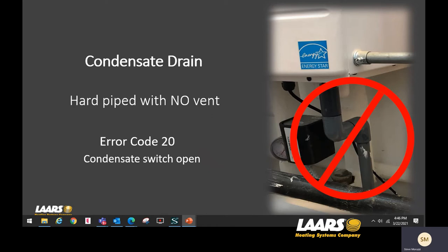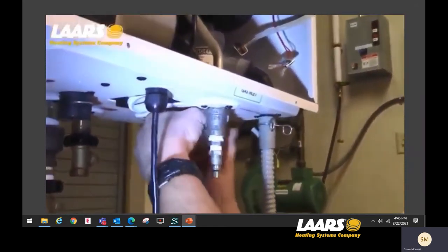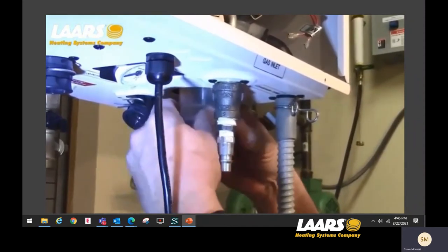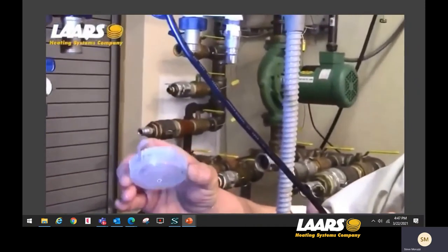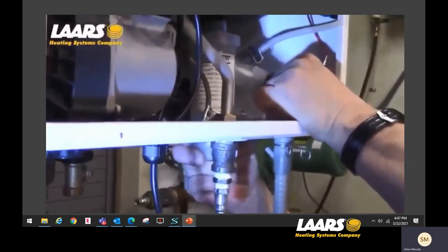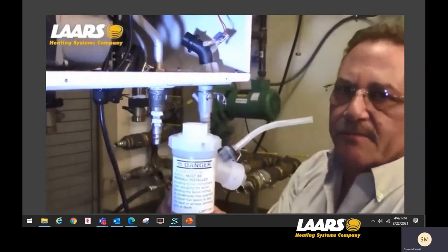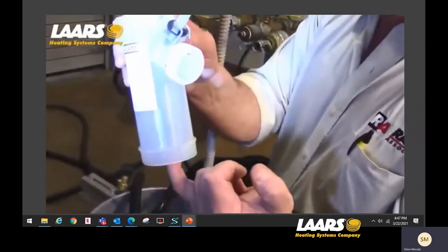If you've got error code 20, check for blockage. If not, check whether the installer used hard piping instead of our condensate hose and make sure there is a vent in that pipe. Here is a video of removing the condensate trap, which is constructed of two pieces — the lower clean-out can be removed and there will be some water in it. Clean out the bottom drain cover, reach up into the bottom of the boiler, and once the condensate hose connection is removed the trap comes out in one piece. Turn it over and assure the bottom hole is free of debris and that the float inside travels freely.